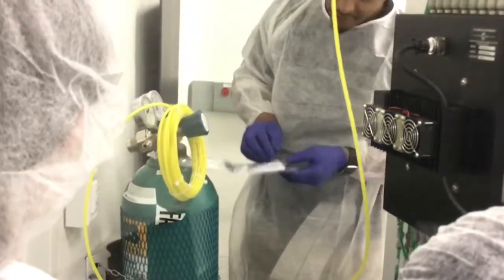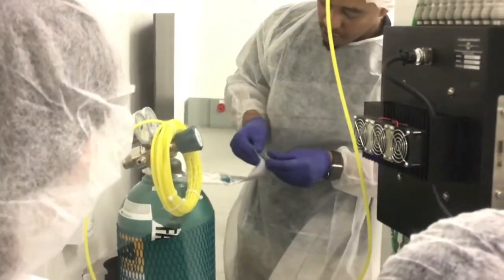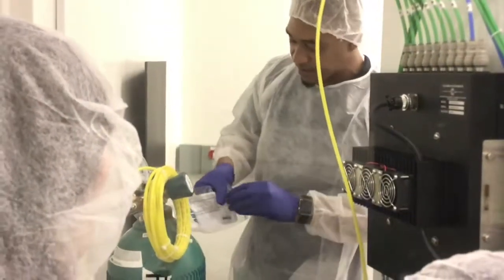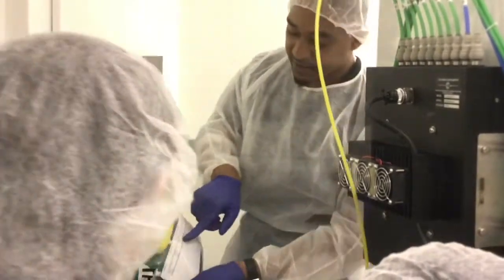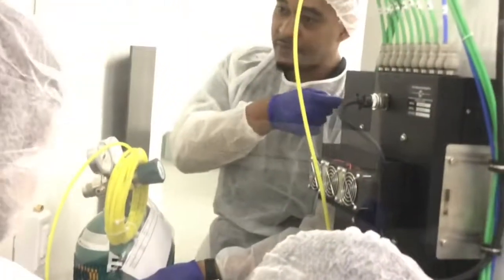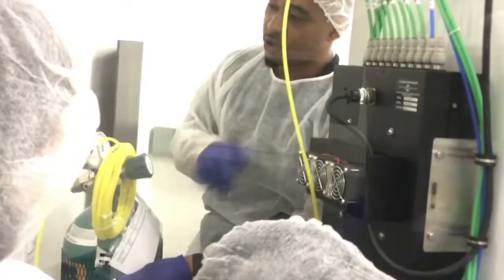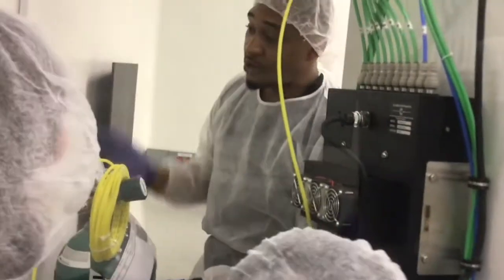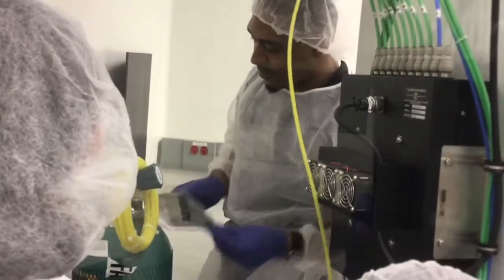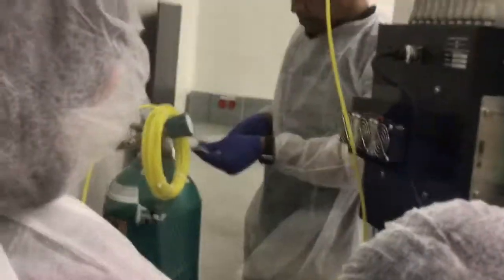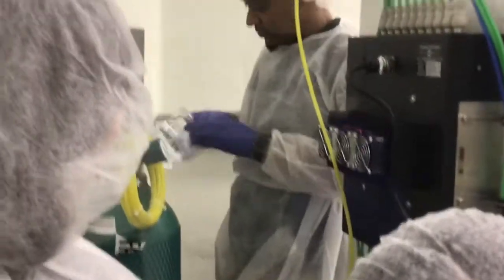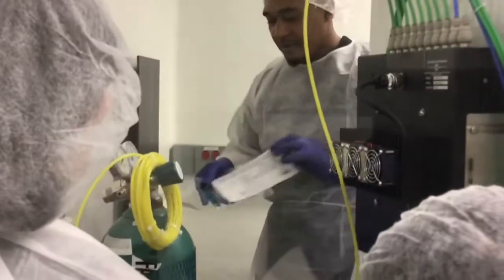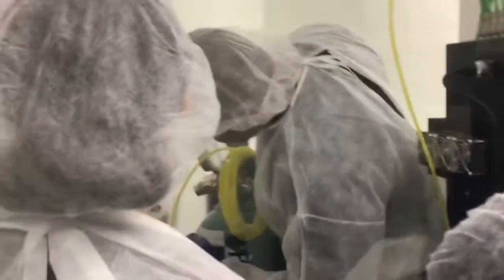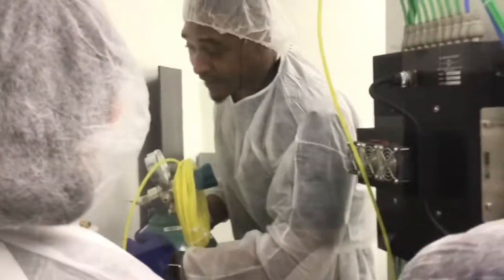Oh, important: calibration gas. Right now you won't need this, since I've already entered these numbers in the system, on the calibration window, so it saves them. If you happen to get some new gas, don't use the same number, because this is what happens with these. Most people just look at the tag here and go by this number. The number here is what you asked for.